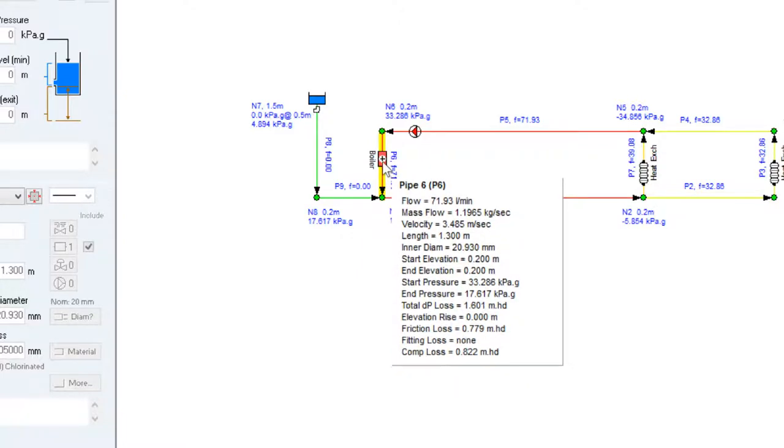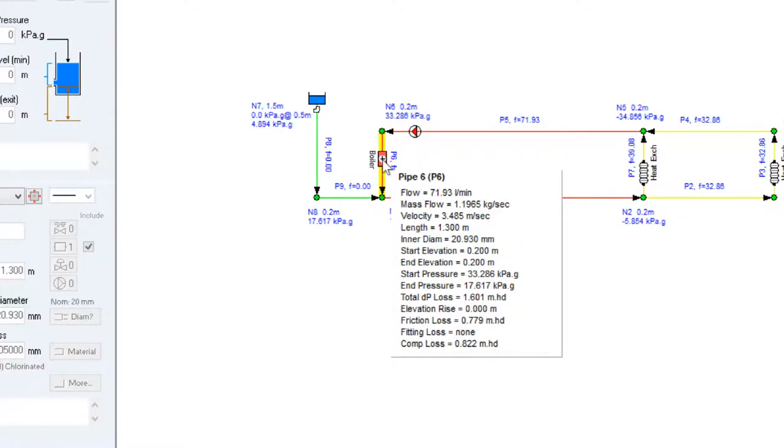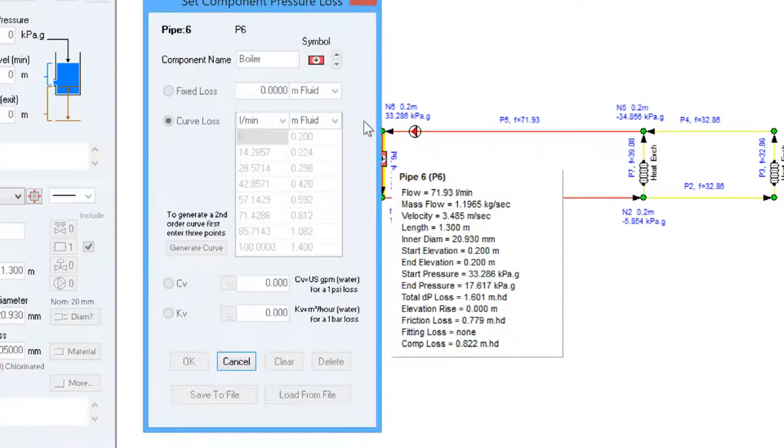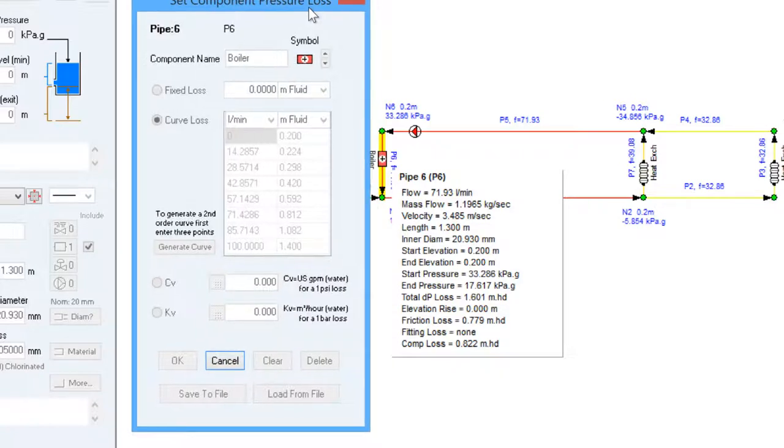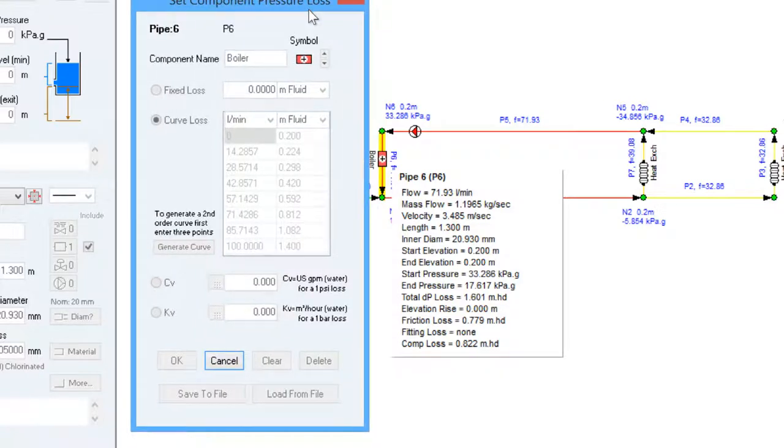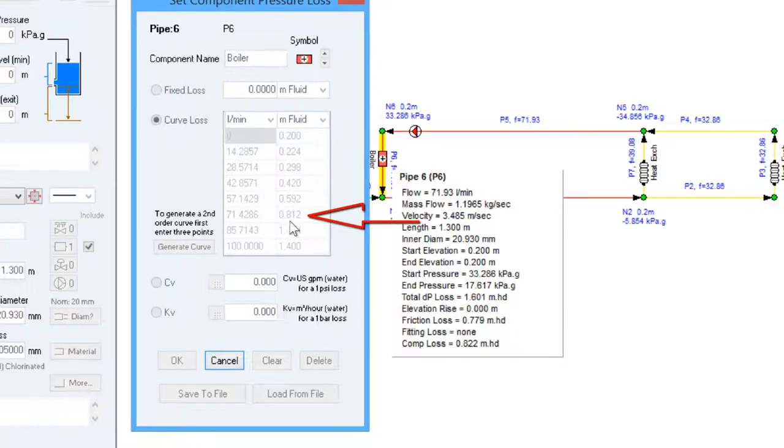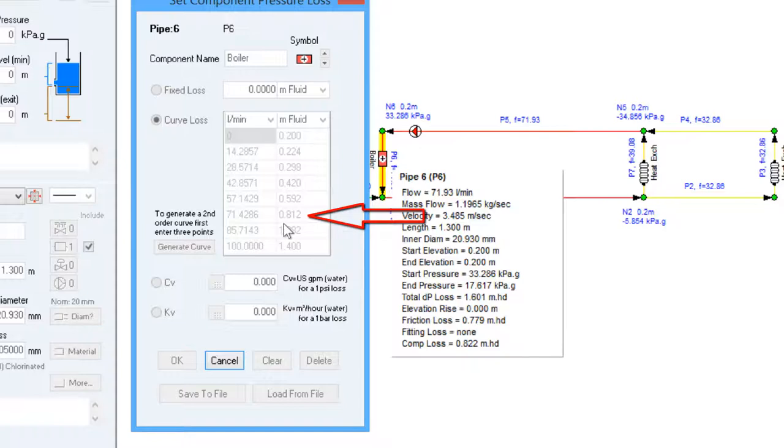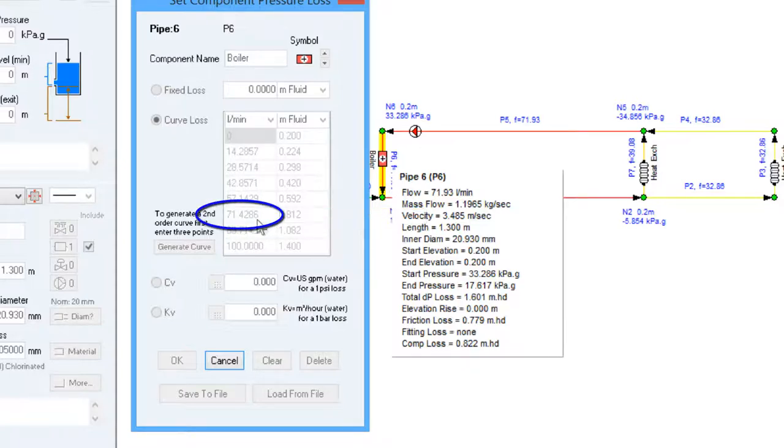And we can then click on the boiler icon itself and we can look at the performance curve for this component and find the point that corresponds to our component loss that has been calculated and see that we would expect to flow just over 71 litres per minute for this pressure loss.